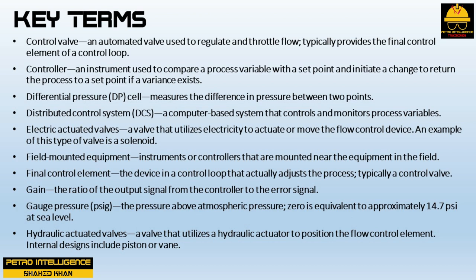A distributed control system (DCS) is a computer-based system that controls and monitors process variables. An electric-actuated valve utilizes electricity to actuate or move the flow control device; an example is a solenoid valve. Field-mounted equipment refers to instruments or controllers mounted near the equipment in the field. The final control element is the device in a control loop that actually adjusts the process, typically a control valve. Gain is the ratio of the output signal from the controller to the error signal. Gauge pressure (PSIG) is the pressure above atmospheric pressure; zero is equivalent to approximately 14.7 PSI at sea level. Hydraulic actuated valves utilize a hydraulic actuator to position the flow control element; internal designs include piston or vane.